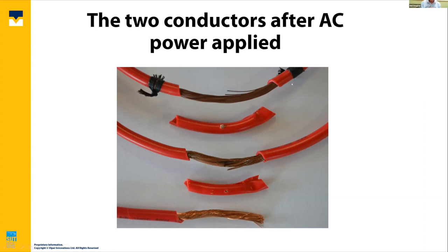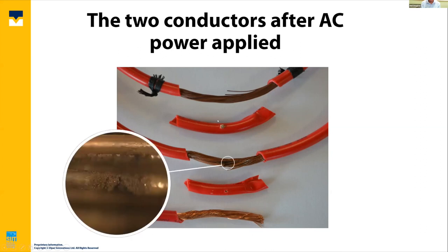So this is L1, this is L2, and down here I've got some pristine copper, so you can see it is untarnished. So what we're seeing here is tarnishing of the copper, and this is not when we opened it up, this is happening within the seawater. And again, you can see that some of the strands on both of the wires are breaking. So if we again zoom in, hopefully that is visible to you, but you can see again, these breaking wires are not as a result of us stripping back the plastic.